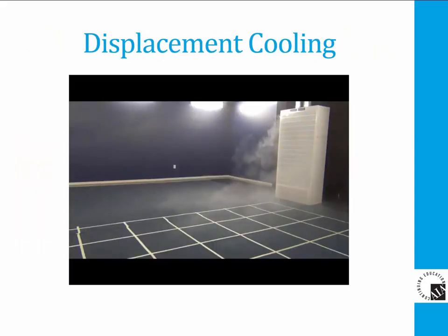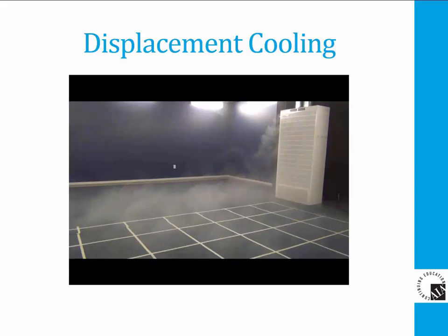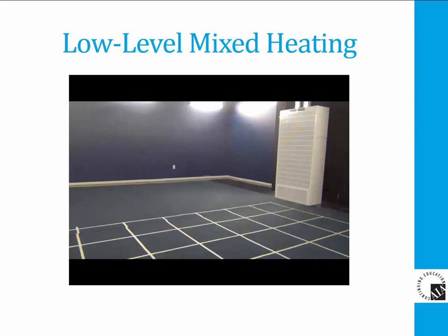This video shows a low velocity of air being discharged into the space. When supply air is at least 2 degrees cooler than the space air, air will cascade downward to the floor and slowly travel across the floor until reaching a heat source where it will then stratify. This smoke video shows the warm air being distributed across the floor from the lower chamber during a call for heat.